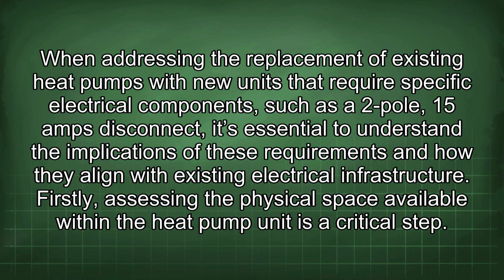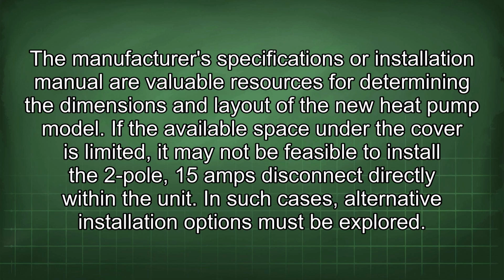Firstly, assessing the physical space available within the heat pump unit is a critical step. The manufacturer's specifications or installation manual are valuable resources for determining the dimensions and layout of the new heat pump model. If the available space under the cover is limited, it may not be feasible to install the 2-pole 15 amps disconnect directly within the unit. In such cases, alternative installation options must be explored.